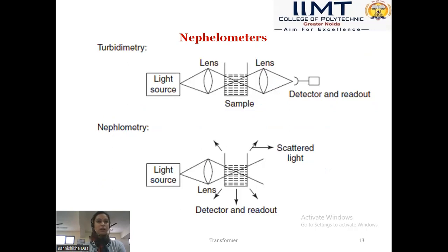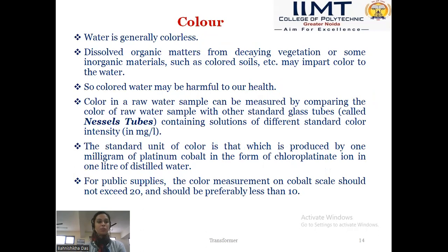It is a digital turbidity meter, which gives the value digitally; the reading is displayed on the instrument itself. So these are the various instruments which are used for turbidity measurements. Nowadays, nephelometers are mainly used for measuring turbidity because it is a digital meter. It gives a very accurate value of very low turbidity. Even if the turbidity is very low, for drinking water samples up to 1 unit or 1 ppm, that turbidity can also be measured using nephelometers.